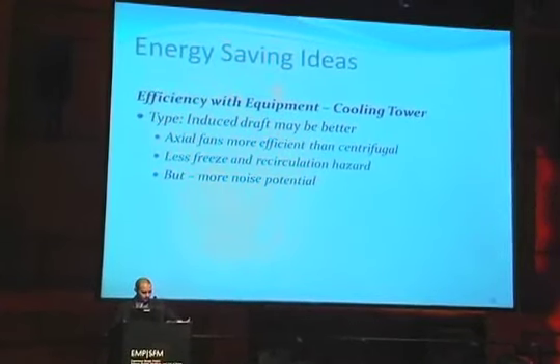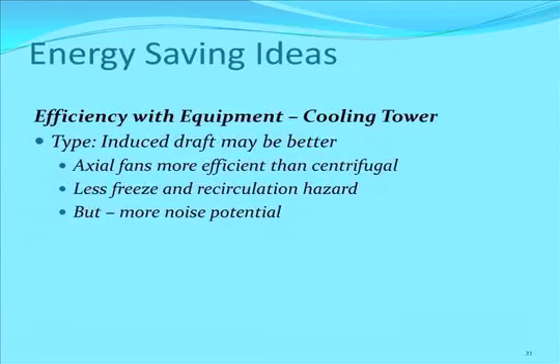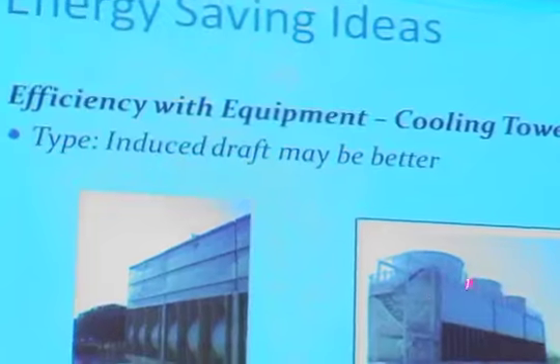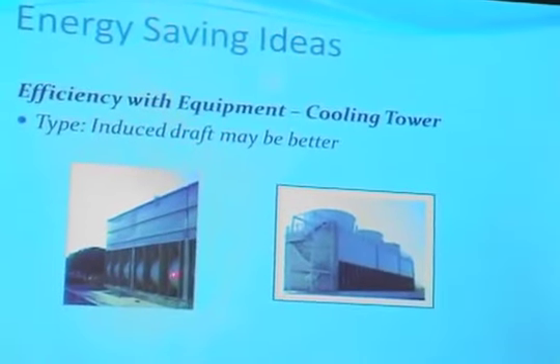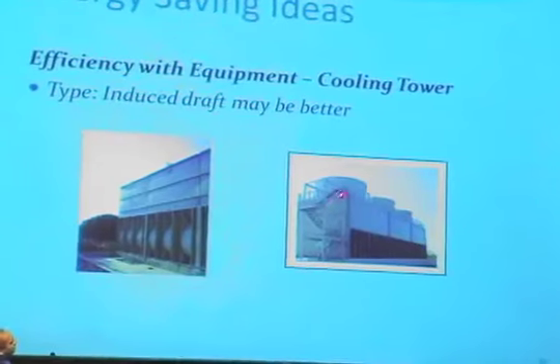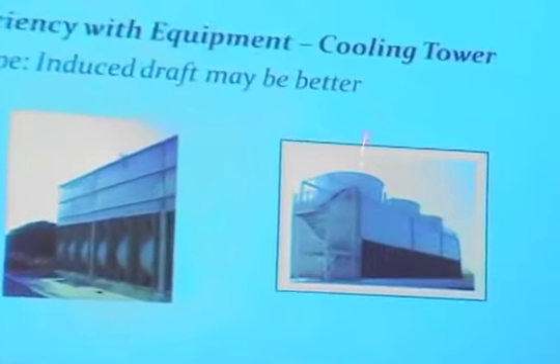Going on to the focus here with the cooling tower, induced draft might have benefits here because axial fans tend to be more efficient than centrifugal. You have less of an opportunity to have freeze problems. They might be a little noisier, but you can see just by the geometry, here's your forced draft cooling tower, and here's your induced draft. It'll eject the water at a greater velocity, the steam at a greater velocity here, so you have less re-entry problems here, recirculation, and that also, in cold weather, then prevents a lot of your freeze problems.